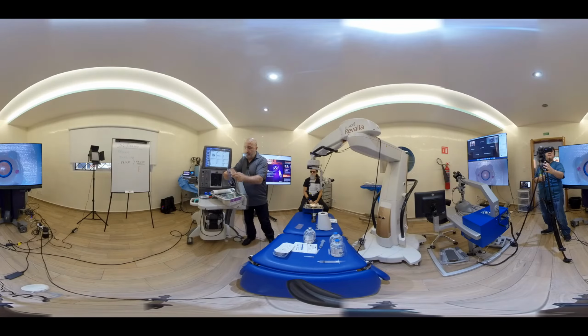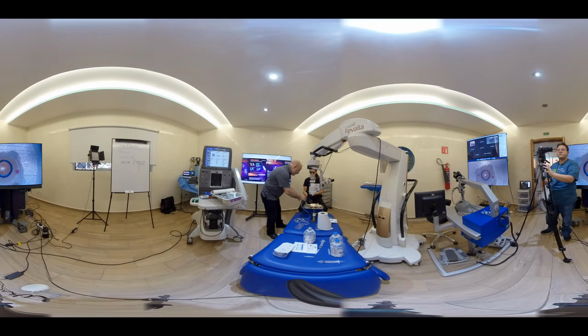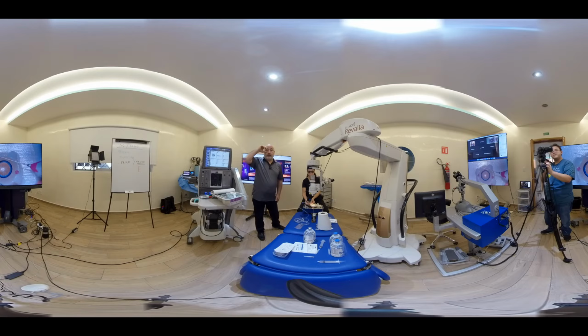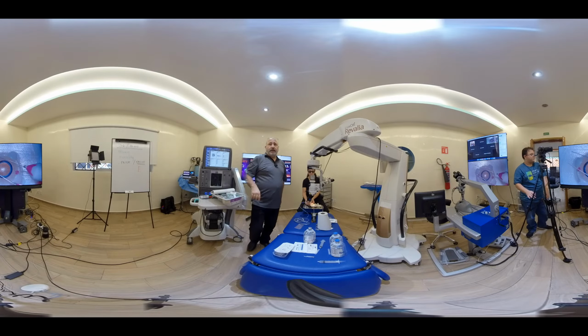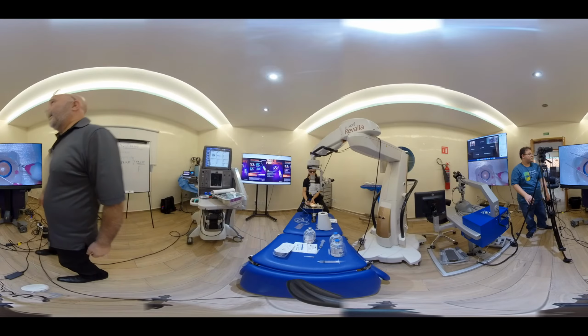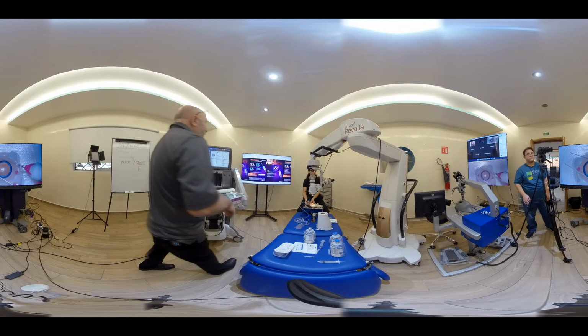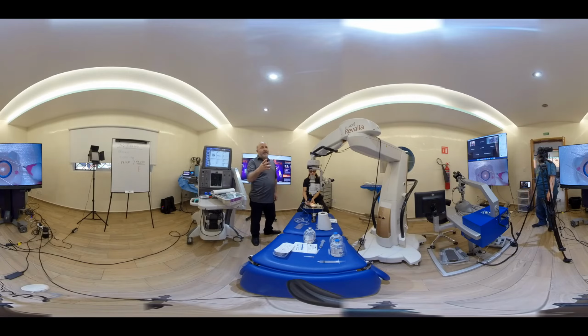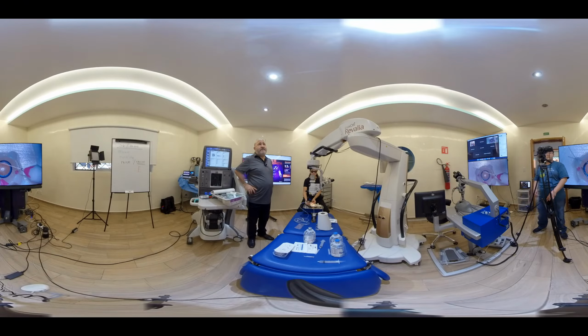Maybe Vanessa, if you don't mind, just showing the difference between the shaft of a light pipe, how long it is, and the shaft of the vitrectomy probe. You can see the stiffening shaft on the light pipe is a lot bigger, so that makes the light pipe much stiffer. This is a light pipe, and this is a vitrectomy probe, and its stiffening shaft is a lot shorter. So you're going to have much better control of the eye using the light pipe, and you use the vitrectomy probe to follow what you do with the eye. Does that make sense? A lot of sense.